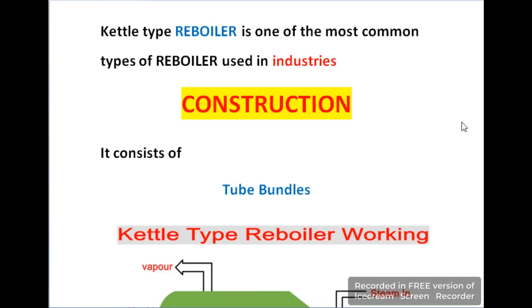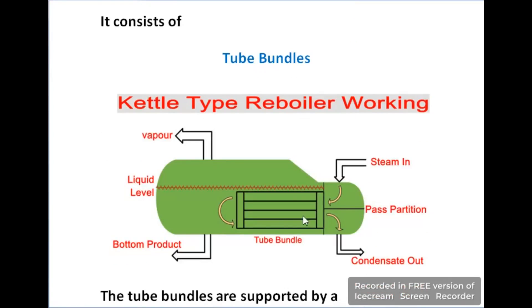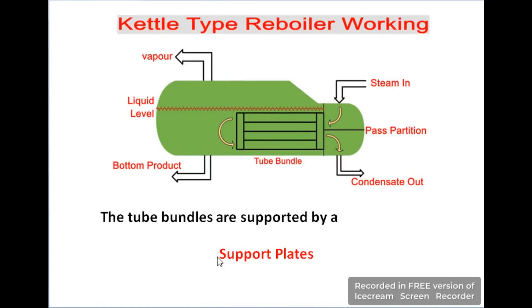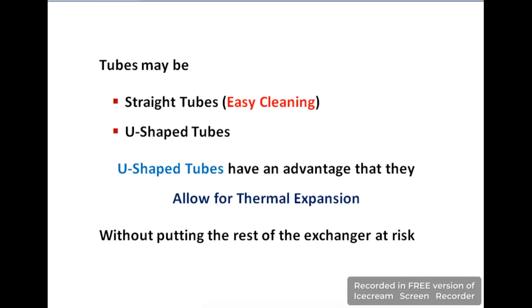Kettle type re-boilers are the most common re-boilers which are mostly used in industries. According to its construction, these consist of tube bundles, which you can see inside the shell. These tube bundles are supported by support plates. The tubes fitted in the kettle re-boiler shell may be straight tubes or U-shaped tubes. If the tubes are U-shaped, they allow for thermal expansion and the heat exchanger will not be at risk.